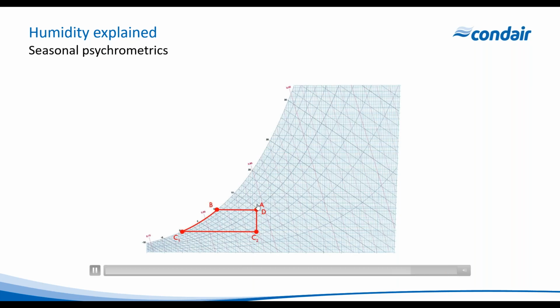And this is the cycle. If we've got a space condition at 21 degrees C and 50%, and outdoor air is at 10 degrees C, then we'll be at saturate. As it gets colder, the RH will remain at 100%, but our moisture content will be low. And as we heat that air up to 21 degrees C, our relative humidity won't be able to satisfy. So we have to humidify up to 50%.